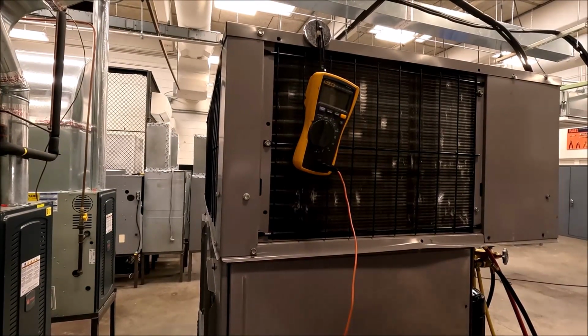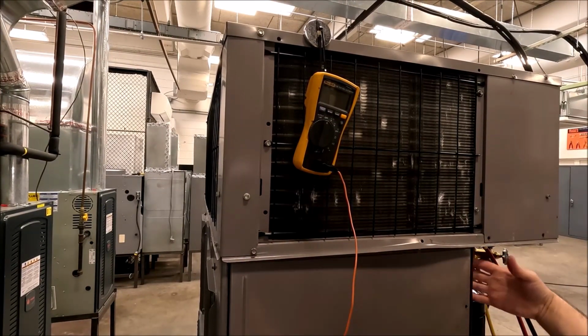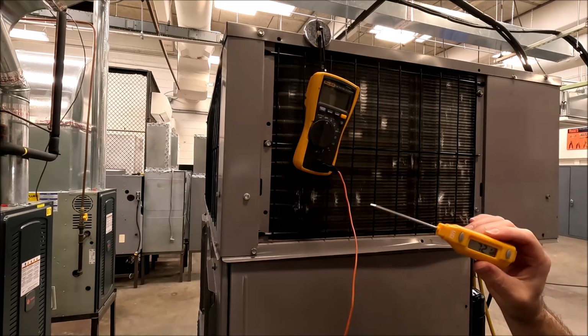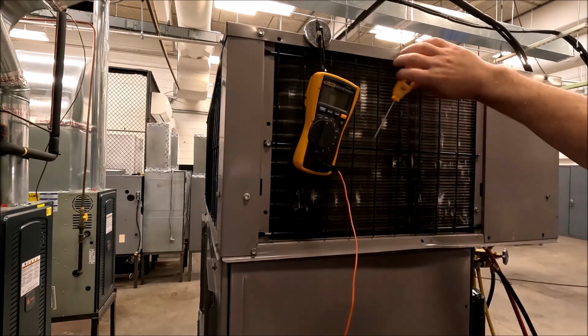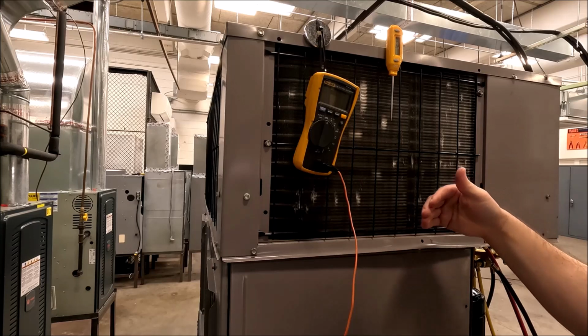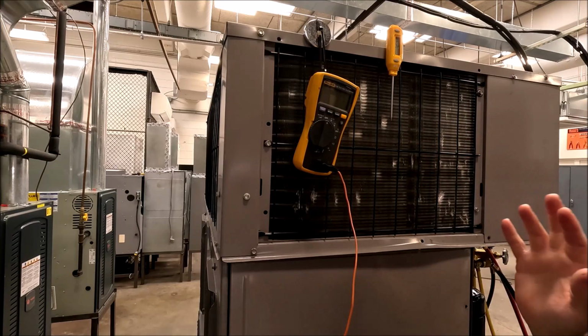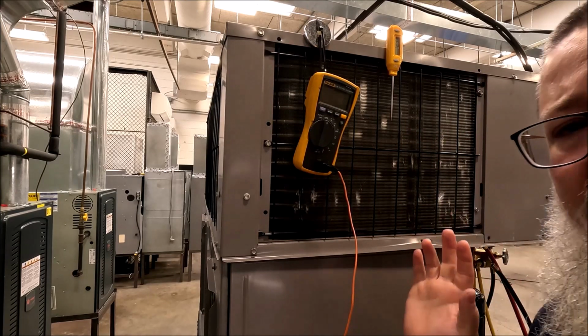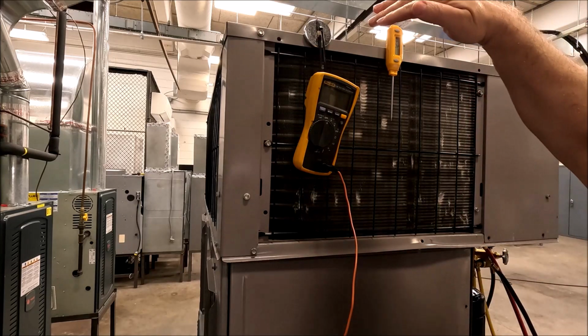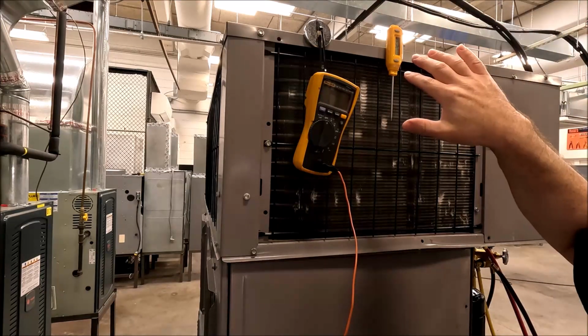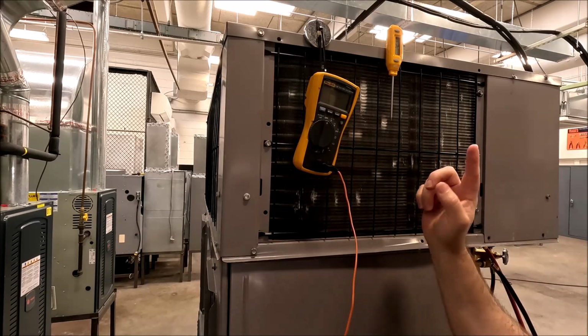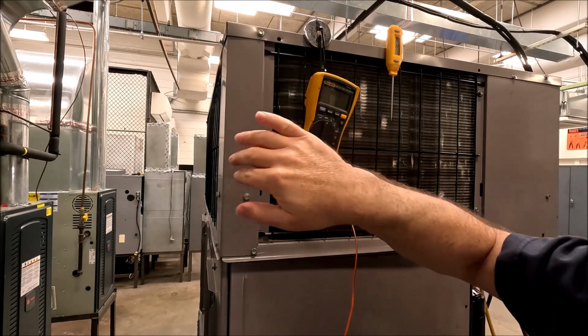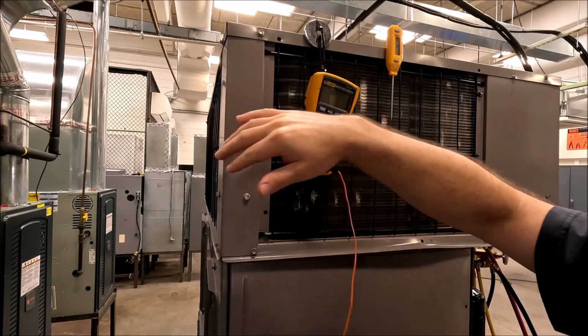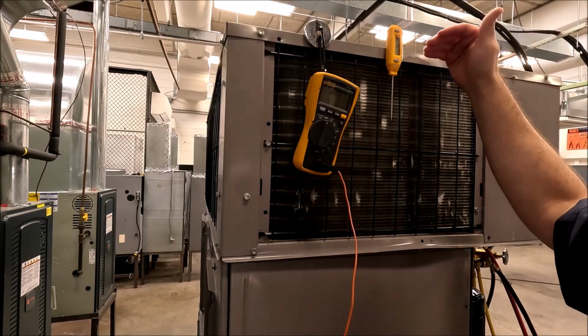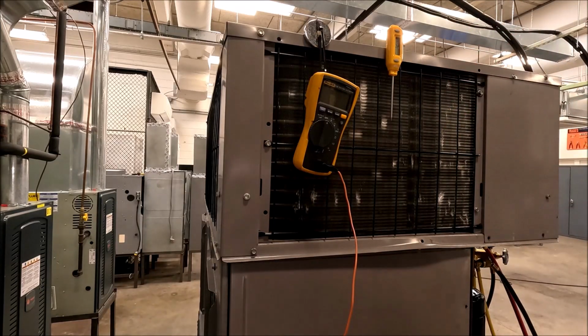All right, so here we are just around the corner from the compressor area, and what I would do is take my little air thermometer, turn it on and stick it right here by this side, especially if it's not in the sun. You don't want a direct sunlight reading, but if you could either shield it or put it on a side of the condenser coil, because this whole top is the condenser coil, right? So somewhere around the corner would be a good spot. Let that start getting your condenser temperature, or at least the air going over the condenser.